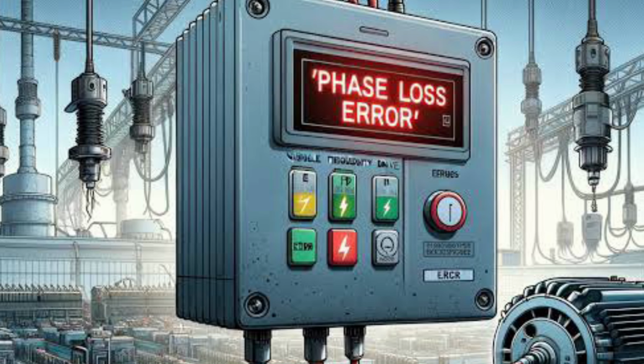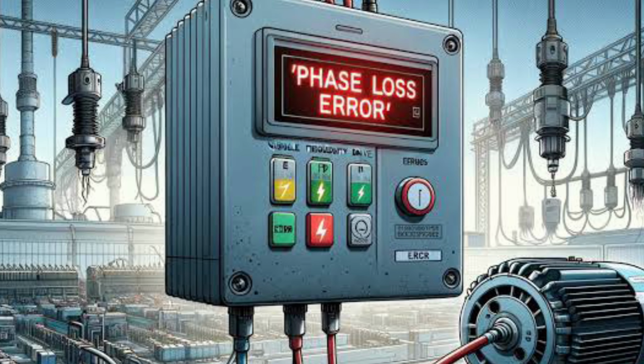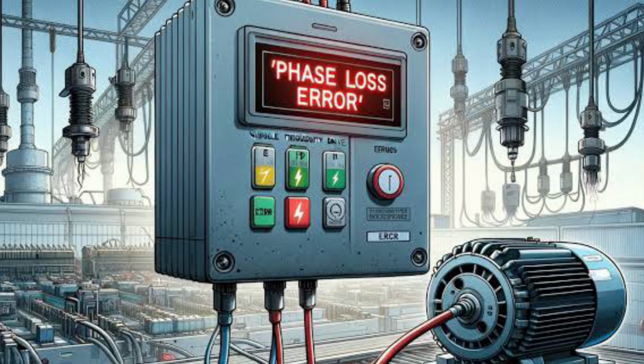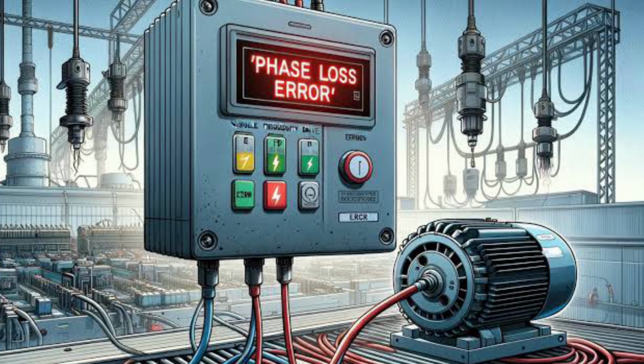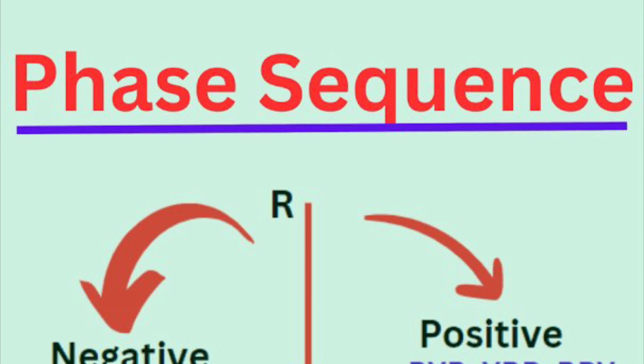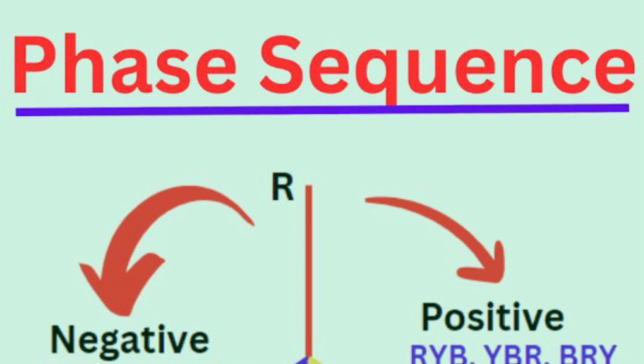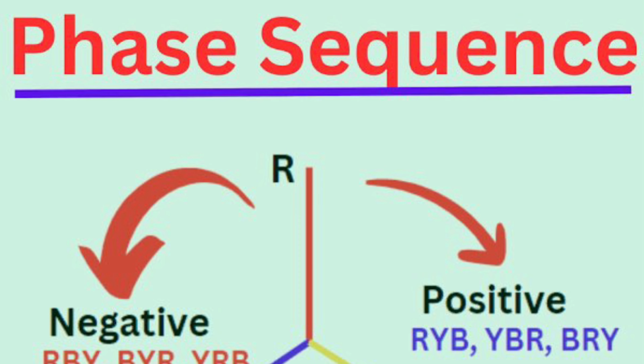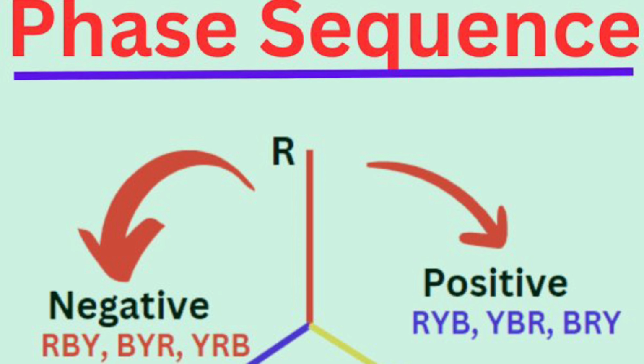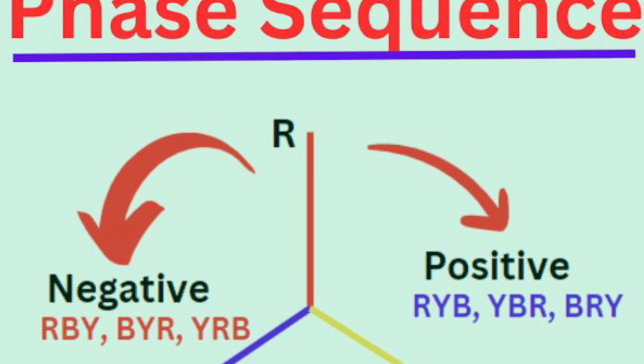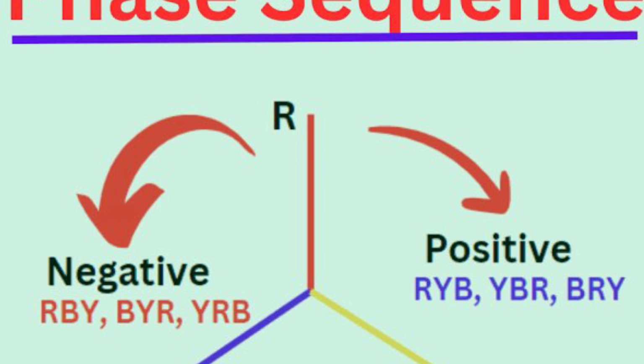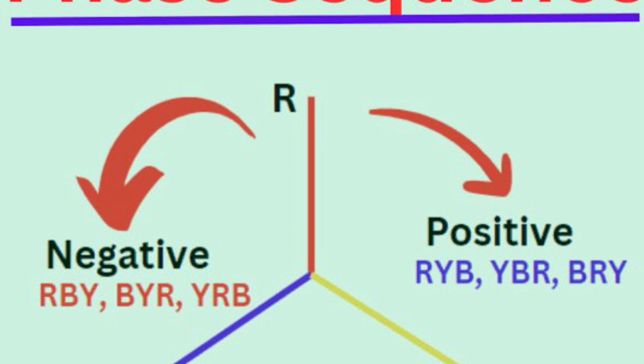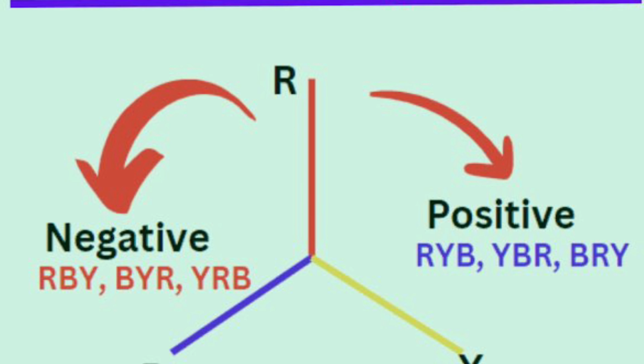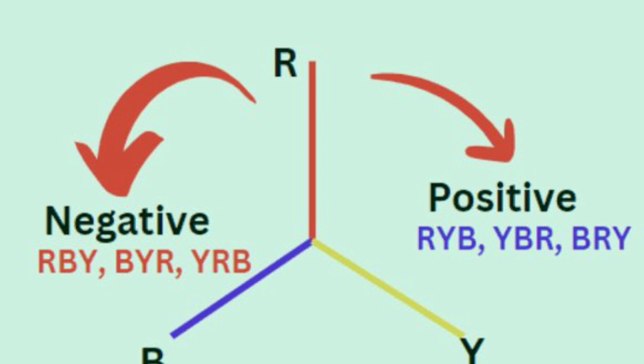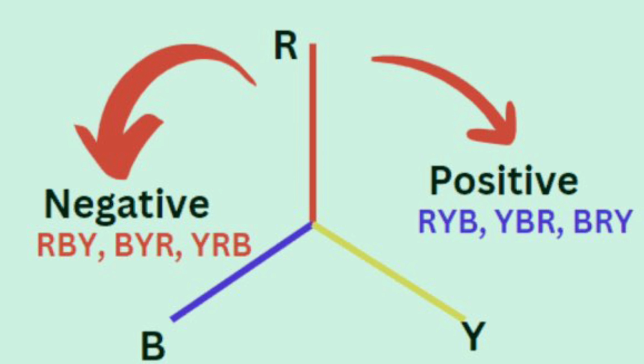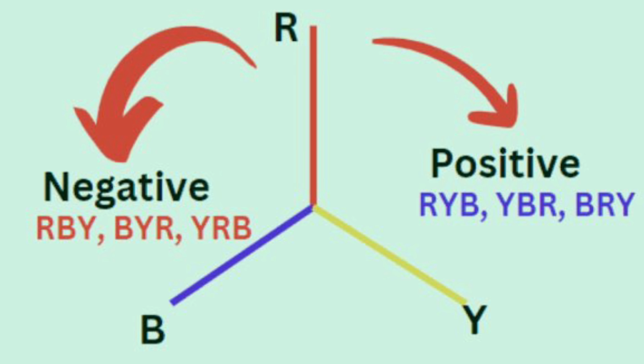So, on the input side, out of 3 phases, if any phase loss occurs, so if any phase is missing, this device will not start the motor and saves it from burning. This device will also protect from reverse phasing. If the sequence of the phase changes from RYB to YRB, then the motor will run in the reverse direction. This device protects the motor from the reverse phase. If the phases are not in a proper direction, then this device will trip the motor.